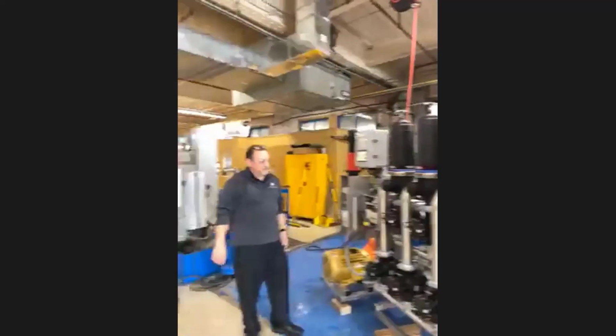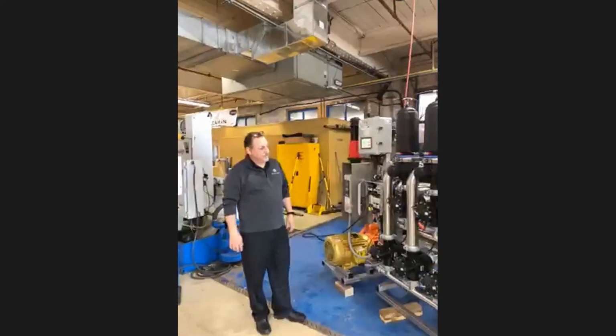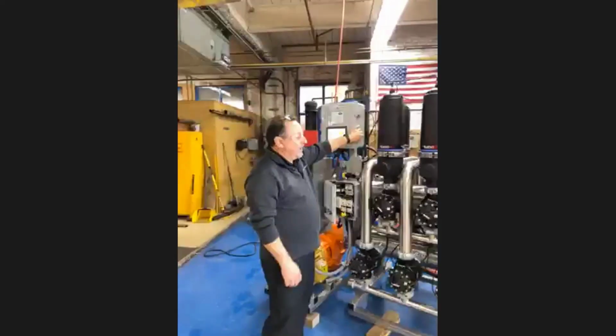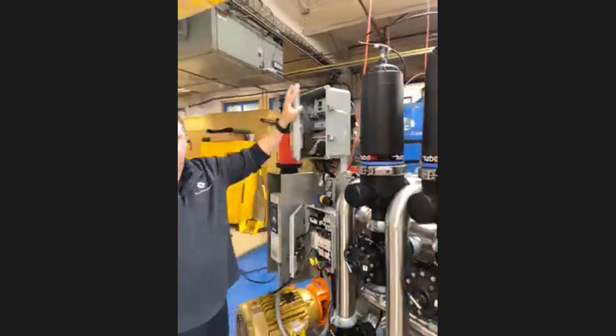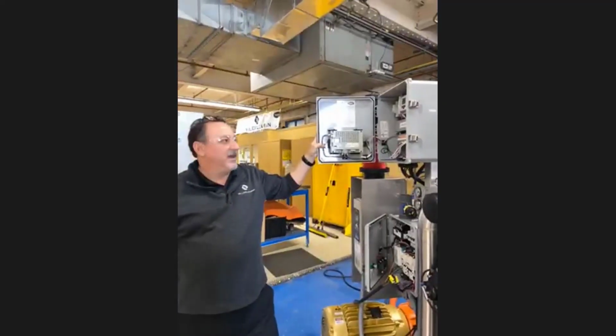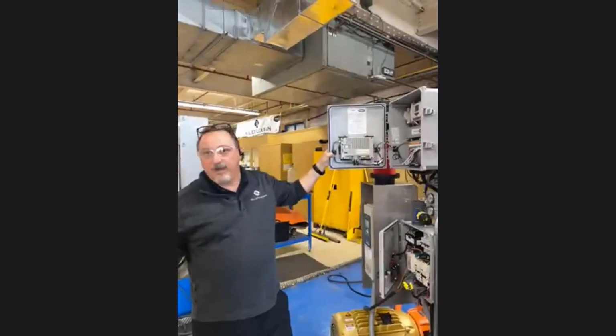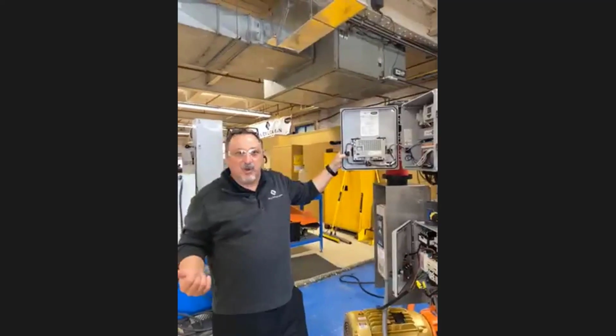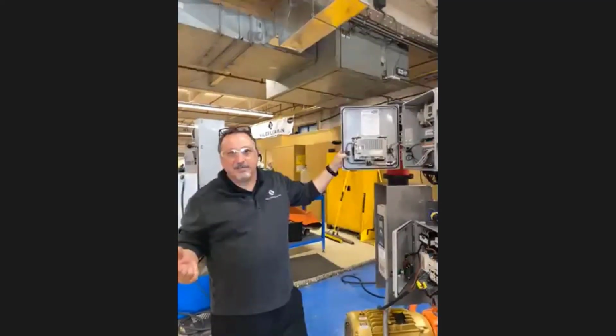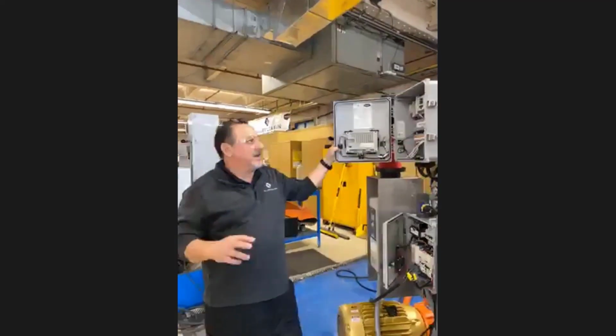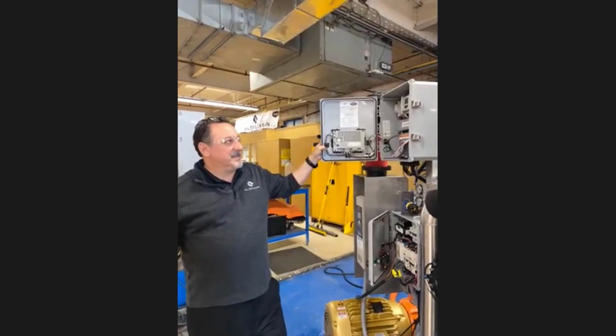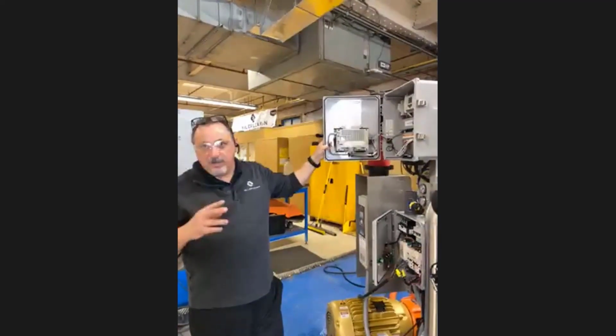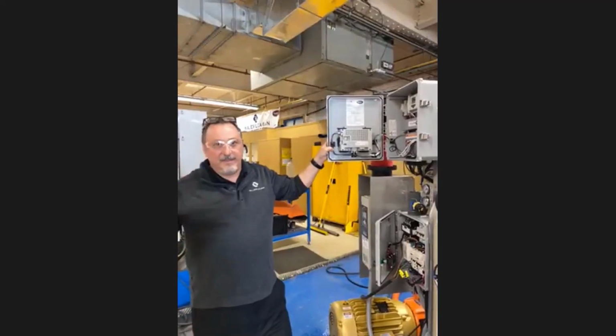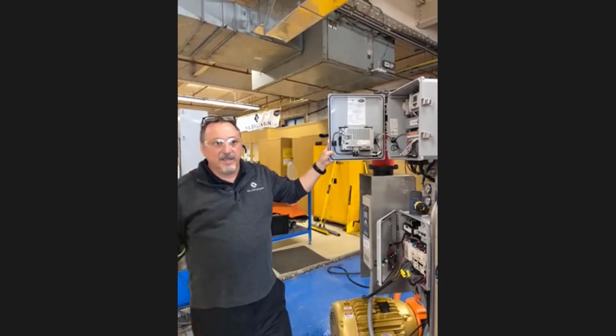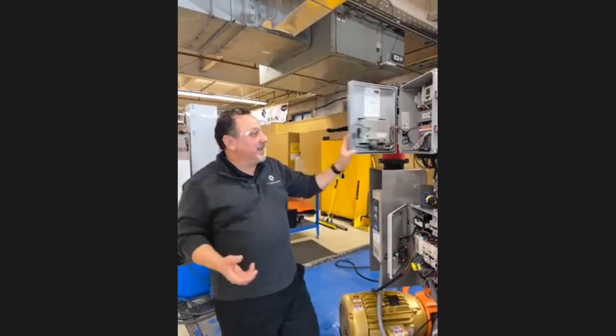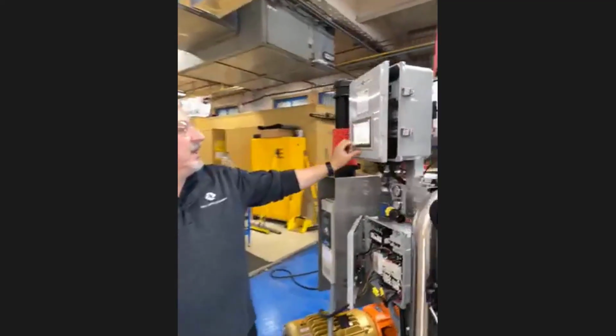Specifically on the controls, obviously you've talked about that one being Allen Bradley. What are the interface capabilities that you have within the different control systems for BMS capability? Really anything they would like. Most of the time we are asked for BACnet or for Ethernet. So they come with both, whatever you would like. You just need to let us know in advance what you want, because we're not going to provide probably a BACnet card unless it's asked for in advance. Ethernet is standard. That comes off the Allen Bradley Micrologix automatically. It's the BACnet card that we would have to provide for you. And that's all installed in there. The Ethernet plugs into the BACnet, and then the IPs, whatever, we give them the chart with all the IP numbers, and they can get any information they would want out of it, or emulate, just like we're doing here with the screens. They could do that too.